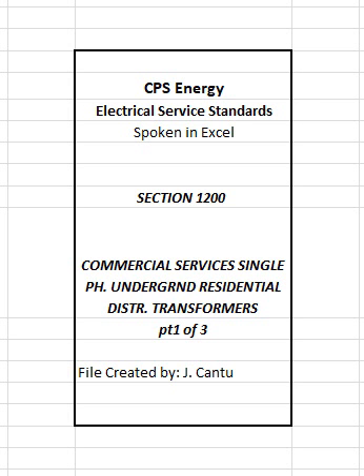Note 1. Where the customer can be served by overhead electric distribution facilities but requests an underground service, the customer will be required to pay the cost difference from that of an overhead transformer service that could serve their load. Note 2. CPS Energy will review and determine in conjunction with the appropriate authority having jurisdiction, AHJ, where it may be necessary to install a transformer in public ROW, i.e. telecommunications and wireless services, traffic signals, bus shelters, etc.